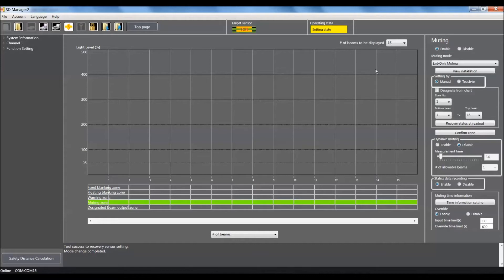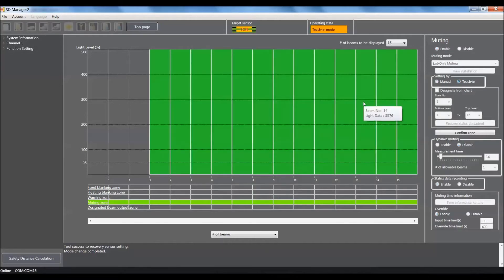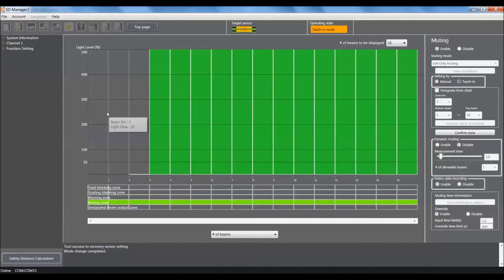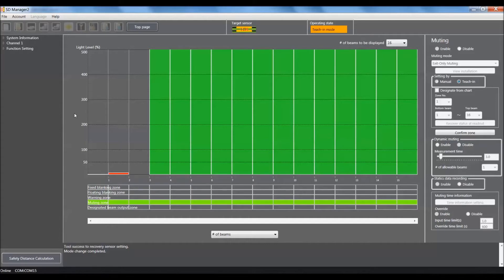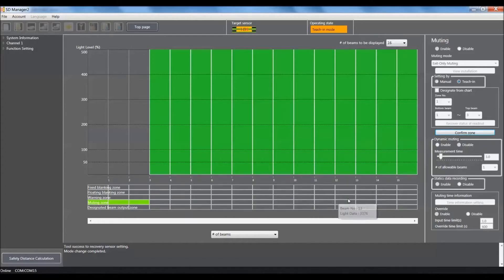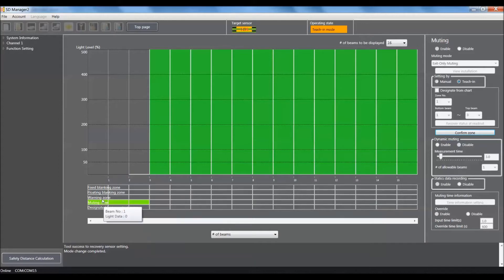We're going to select teach-in and that will visually show us how many beams are being blocked by our object. Right now I physically have three beams being blocked, so I'm going to confirm this zone by clicking on confirm zone and you'll see it shortened our muting zone to only three beams.